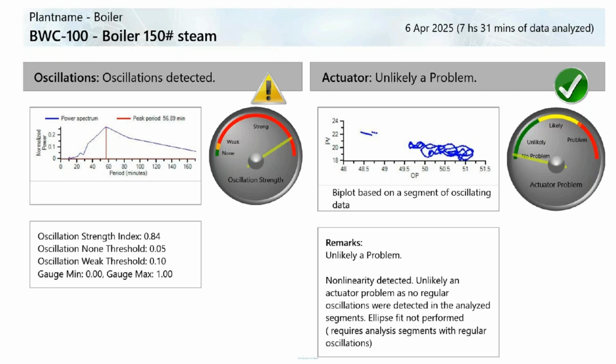As we stated earlier, we've tuned this loop a lot, but it does not seem to help. Maybe there's another cause of this oscillation. As you know, there are 3 reasons a loop could oscillate. It could be due to tuning, actuator, or stiction, or something else upstream. In this instance, the trail is leading to something upstream that's causing the issue.